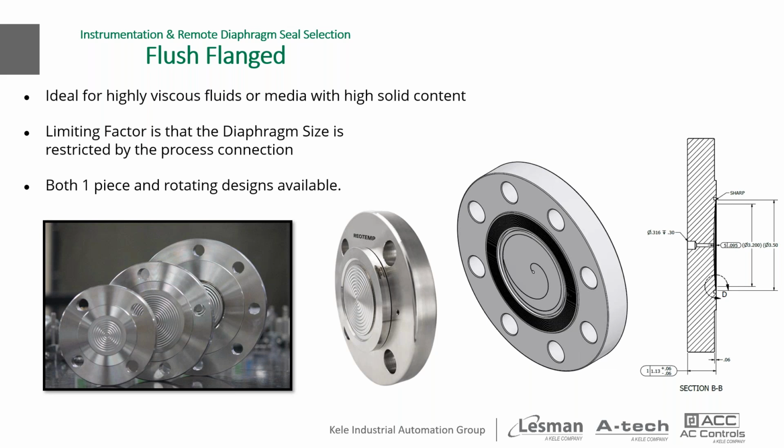The limiting factor is the diaphragm size. It's really restricted to the process connection. You can only get so large with the diaphragm before you start impinging on the raised face.